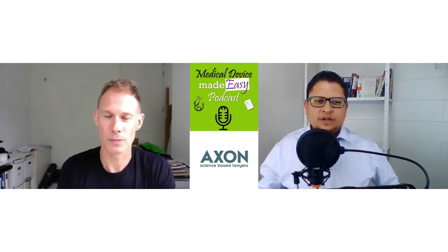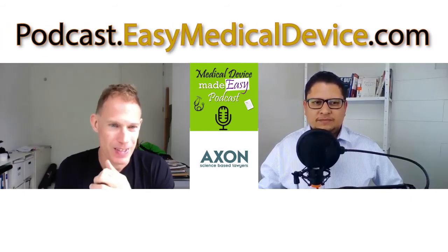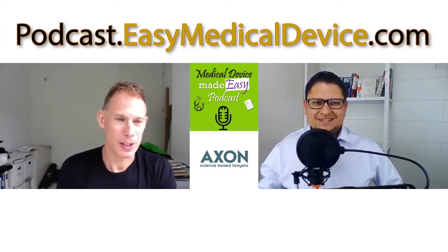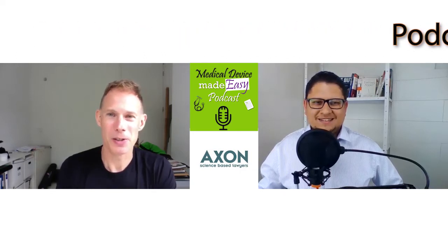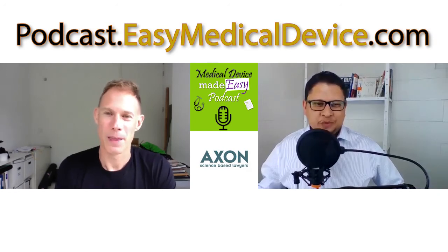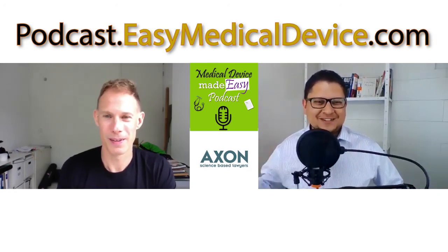So can we say, for example, a person works in one of the manufacturing plants and takes care of another manufacturing plant as a PRRC officially, even if he's not working specifically for this manufacturing plant? Is it something possible? Yes, although, of course, then you go into the intention behind what a PRRC does. And that is, I think, even murkier water, because if you look at the guidance, it says that you need a close linkage of permanent and continuous nature between the PRRC and the manufacturing activities. So you can do that if you prove you are permanently in both places or something like that.